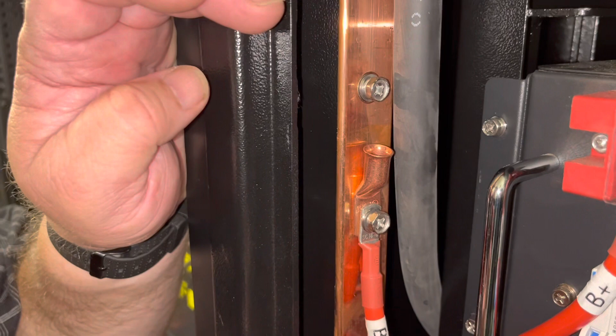Steel bolts and rivet nuts are good for mechanical connections, but you don't want to depend on them for an electrical connection. Now, we're mechanically holding these lugs to the bus bar, so that is important, but you don't want to depend upon that steel nut to conduct electricity, because steel, even though it's conductive, it's not a good conductor.